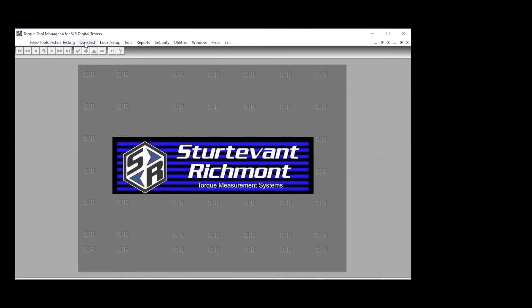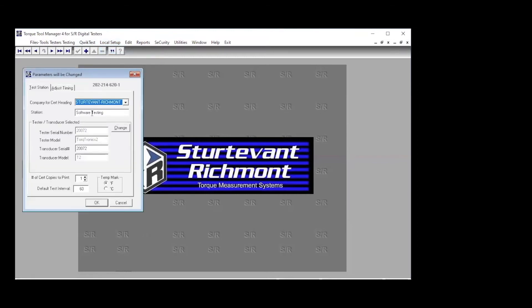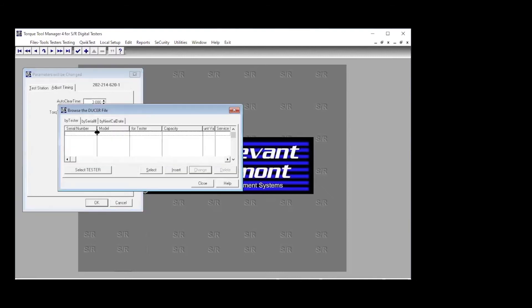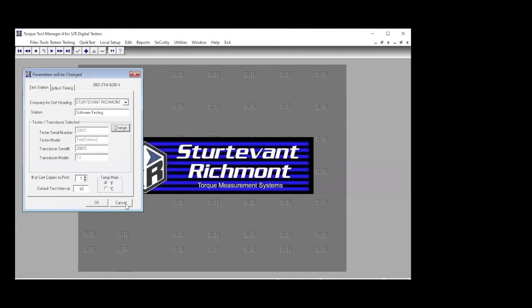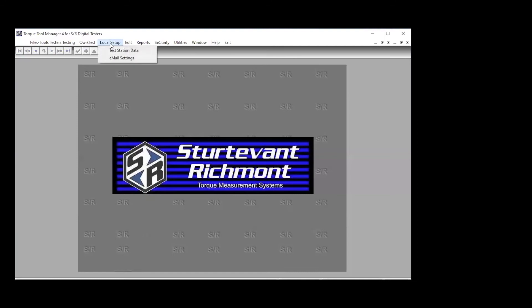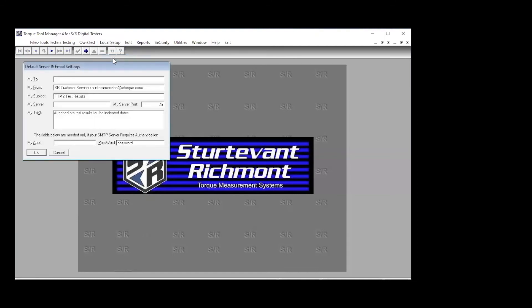We've been through everything. We have led you up to QuickTest. It's important to take a look at local setup. This is two important things. One is we're going to be looking at the testers. And here we were connected to a Torquetronics 2. Here's the serial number, the number of cert copies to print. We've got temperature and the test interval. And then the other thing we can do is we can adjust the timing. Here we have the AutoClear time set to three seconds. Local setup is important. And then the other thing to look at is email settings. And basically, if you're going to be emailing CalCerts, the local setup is the place to set up all of the email. So that once your test is complete, you hit the button, you put the two, you attach it and make sure that you're sending from your email, you hit OK anyway.